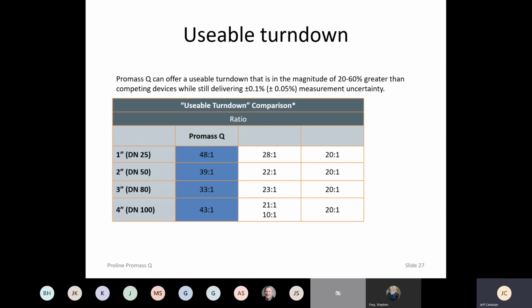Now that doesn't mean the meter goes to zero beyond that. I mean, the meters themselves can turn down extensively, 100-to-1 or more, but your accuracy will start to trail off on mass flow. Remember, a Coriolis meter measures density independently. So density, it does not care about the flow rate at all. As long as the meter is full, it doesn't have to be flowing and you'll get an accurate density reading. Okay, flow still tends to be velocity dependent, and your accuracy will start to drop off at extremely low flow rates.